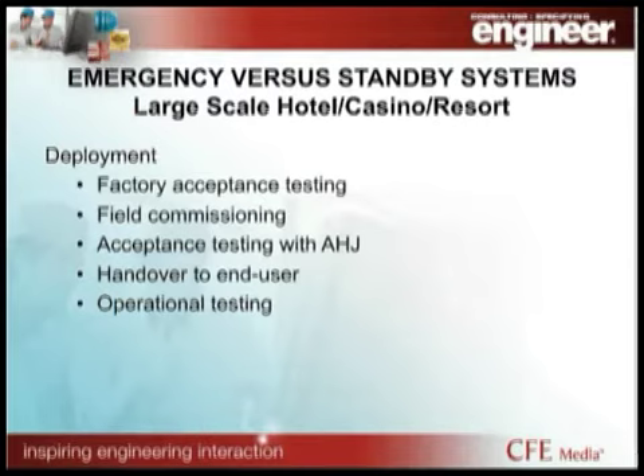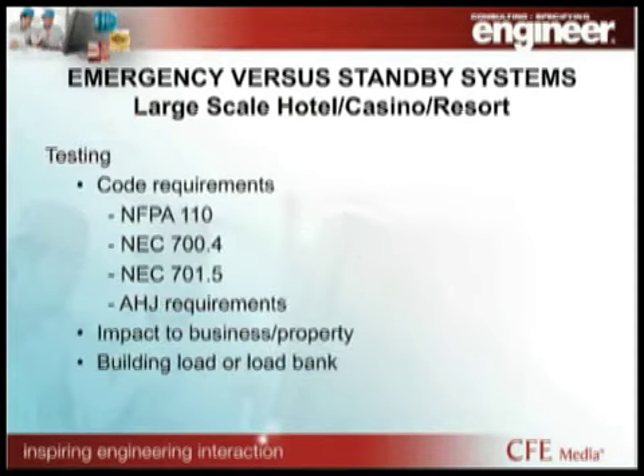Also, at this time, you would want to make sure that you have ongoing maintenance, because this gear is complex. Typically, you're going to have people on site who may be able to maintain it and run it through its monthly testing. But if there's a PLC problem or some sort of real technical problem inside the equipment, you need to have ready access to the vendor and the equipment provider. And then operational testing. NFPA 110 goes into a lot of what you've got to do for testing, and we'll talk about that a little more in the next slide, because operational and functional testing is critical to making sure the system's going to be available when it's called upon to run.